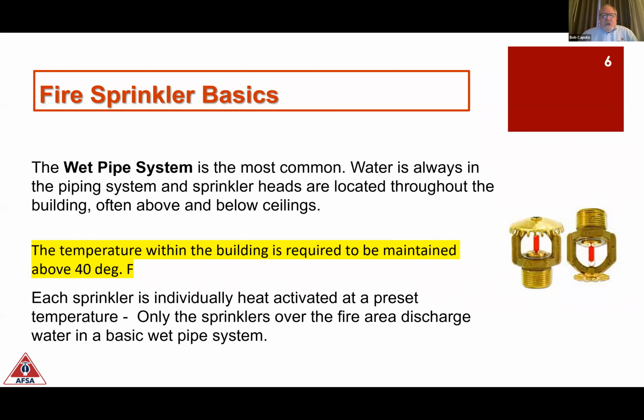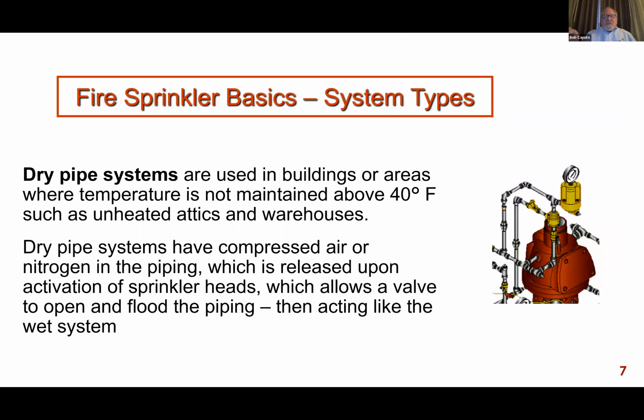For those of you who may not know this, these sprinklers are individually heat activated at a preset temperature. Some are as low as 155 degrees, others are as high as 500 degrees. The standard in most warehouses is going to be 286 degrees. These sprinklers operate fairly quickly, and getting from the 155 to the 286 at the ceiling level is pretty much instantaneous. Very few seconds are needed in the fire between those two temperature gradients, if you will, to operate those sprinklers.